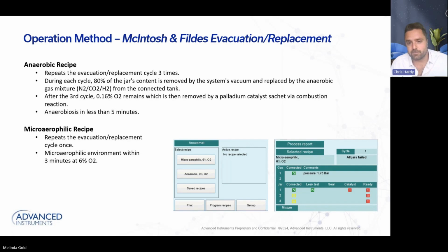Now moving on to the microaerophilic recipe, i.e. the campy recipe, as I like to call it. It does this evacuation replacement 1 time, and hence the less amount of time it takes to create the environment, 3 minutes. And the default O2 level with this environment is 6%.